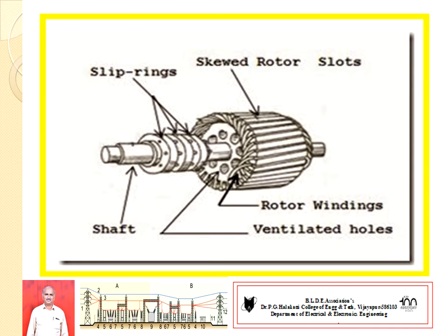So again, this type of rotor also consists of 3 windings. The 3 windings are star connected at one point. The other ends of the star connected windings are connected to 3 slip rings. Through the slip rings, external circuit resistance is also added, because this type of rotor is characterized by low resistance. We can't start the motor without external resistance. Therefore, external resistance is added in series to the rotor circuit via slip rings.